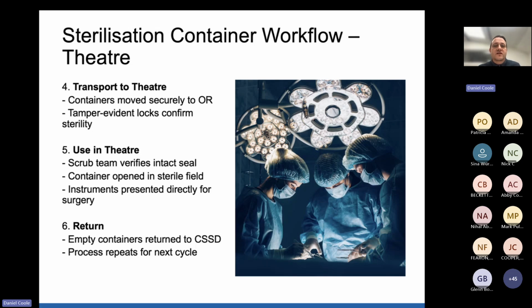So the containers are moved securely to the OR. Often they'll be in a big movable trolley, for want of a better word, that might be locked. The containers move securely, with tamper-evident locks to confirm the sterility, as I showed you earlier, the plastic locks that you have, which are generally disposable. The scrub team will verify that the seal is intact. The container will be opened and instruments presented to the surgeon. Then the empty container is returned to the CSSD, and the process will then repeat for the next cycle.